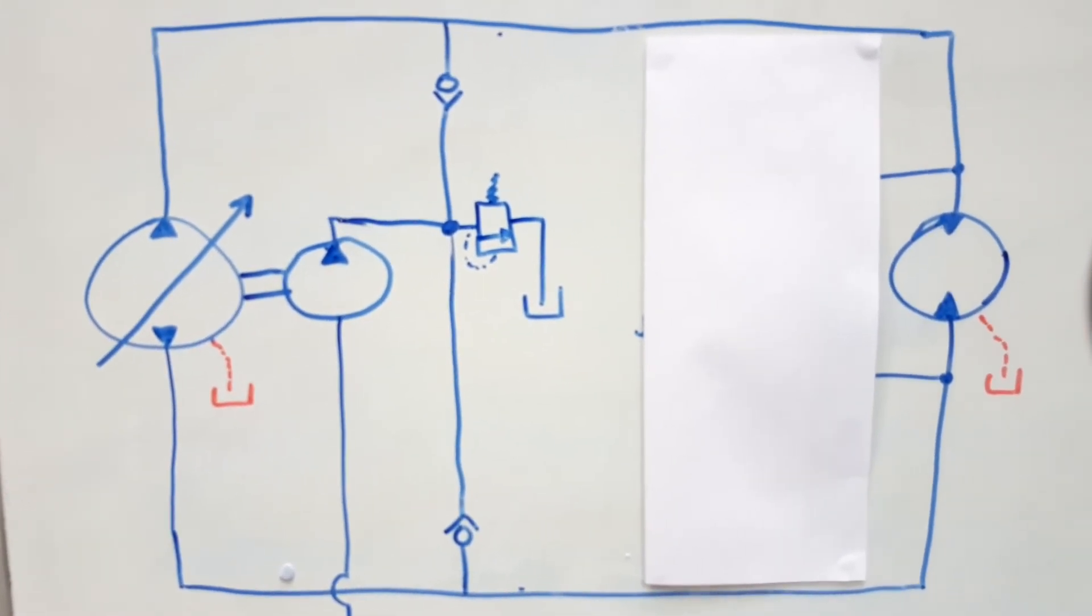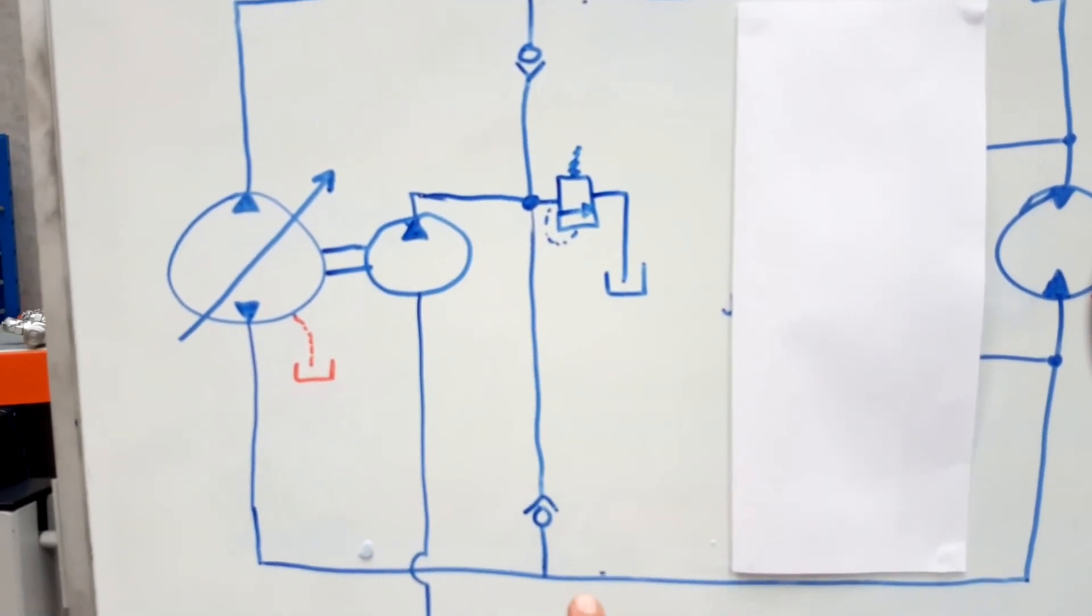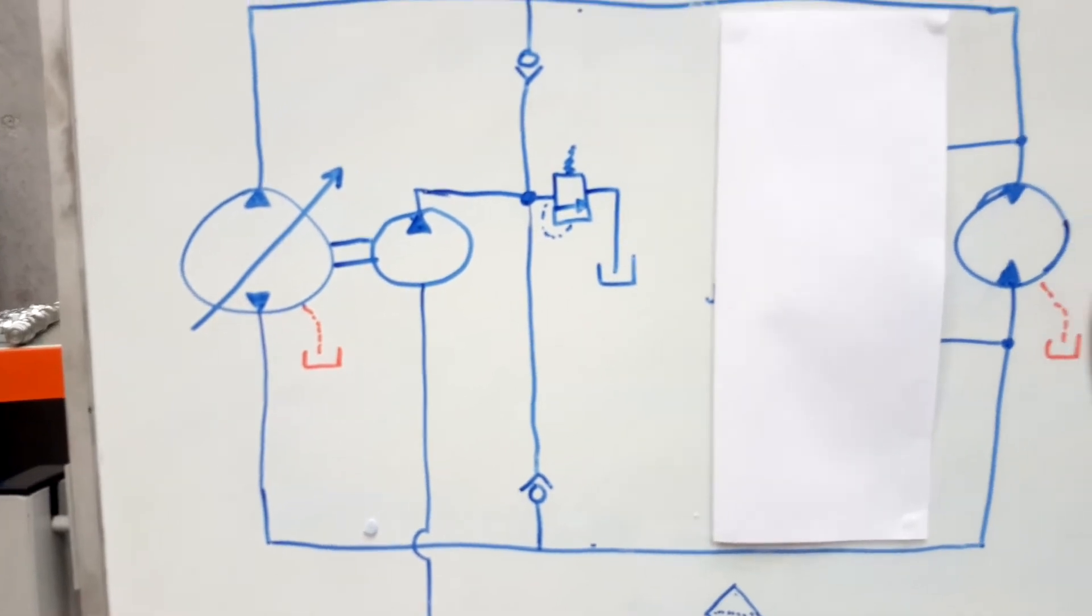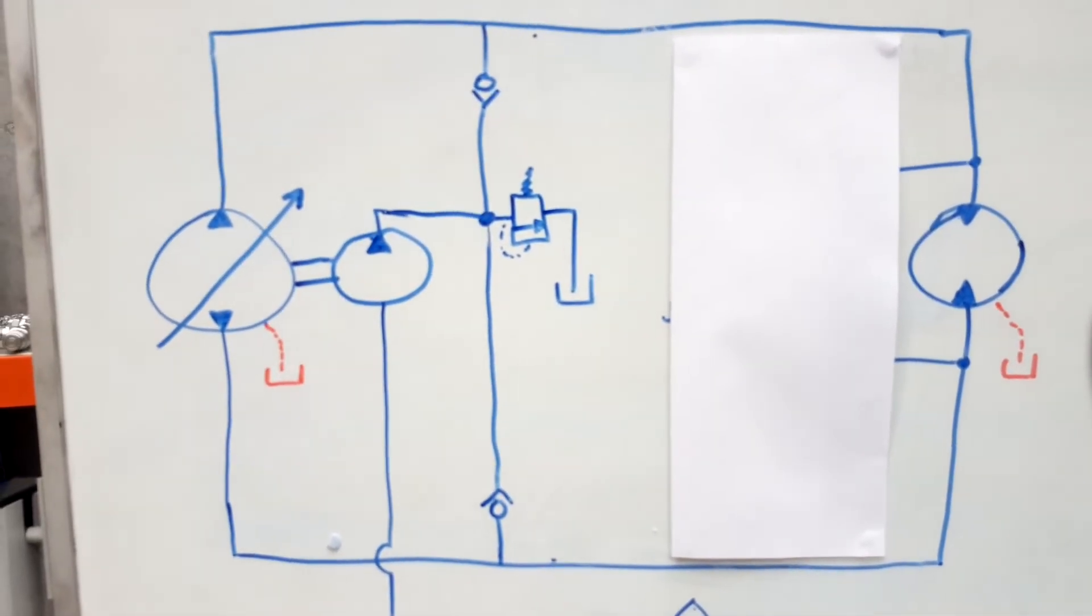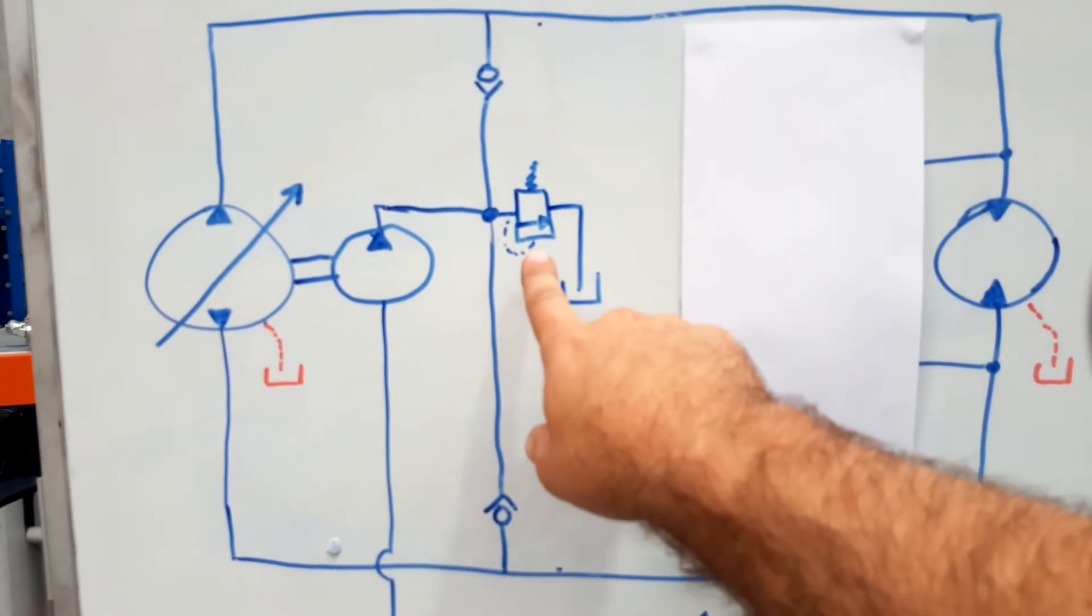So while we have high pressure up here, this check valve is closed and this one is allowed to open, and we can push oil out into the loop and make sure that we keep it full and also help with cooling. Because we have a boost pump here or a charge pump, we've also got what we know as our charge relief or our boost relief.